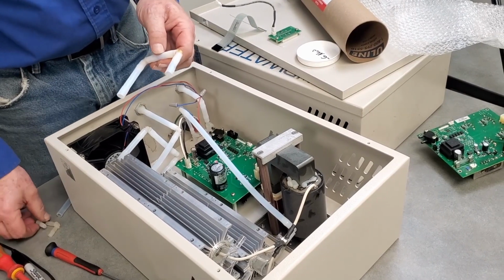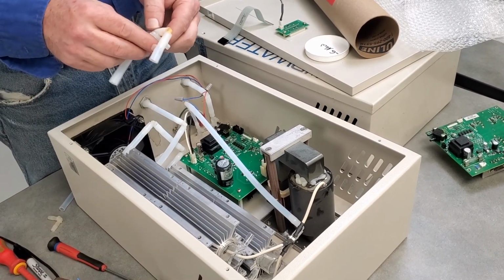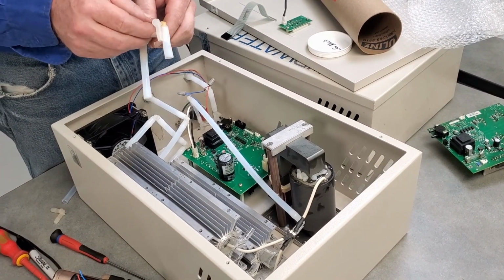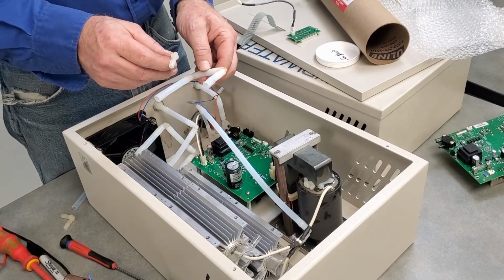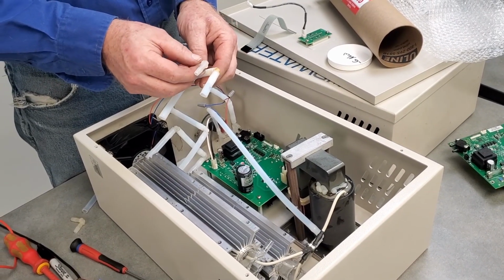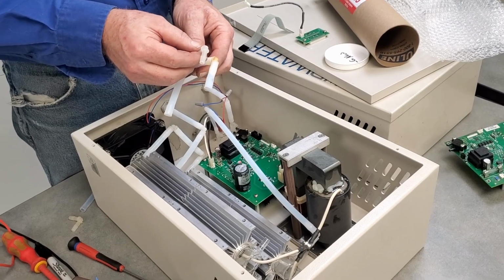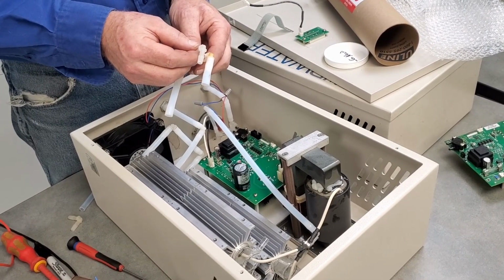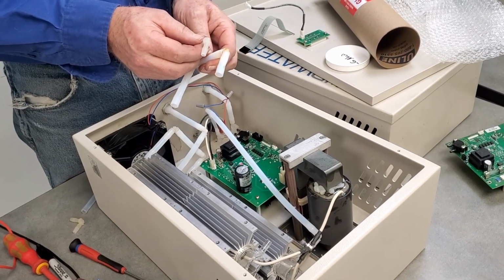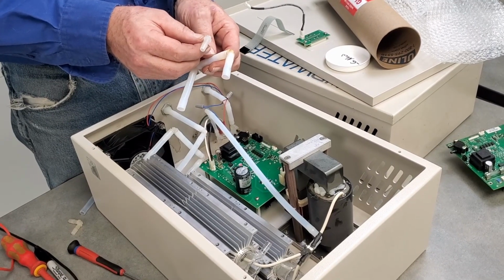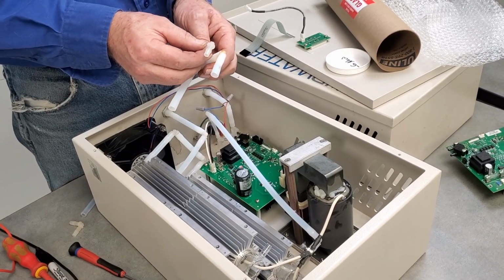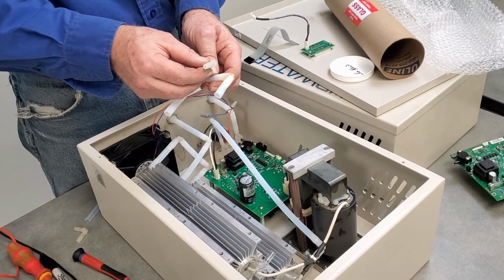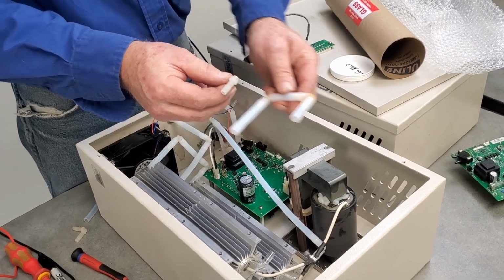With these barb connectors, we have to make sure that they are Kynar. On the newer units, the manufacturer has switched to glass elbows, and the reason for that is the glass is going to be the most resistant to ozone. They're going to hold up the longest. The problem is they're fragile to work with, but this is what we've got to work with here, so I'm going to replace these.